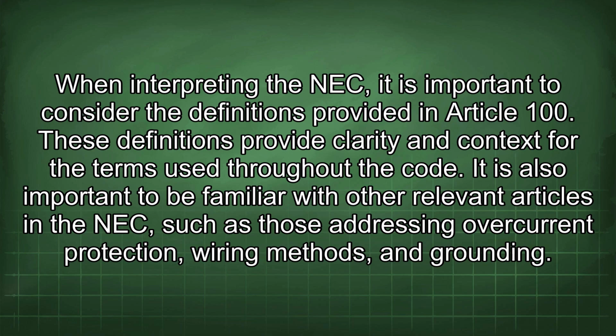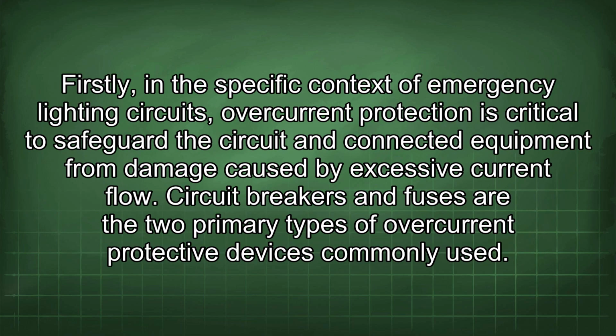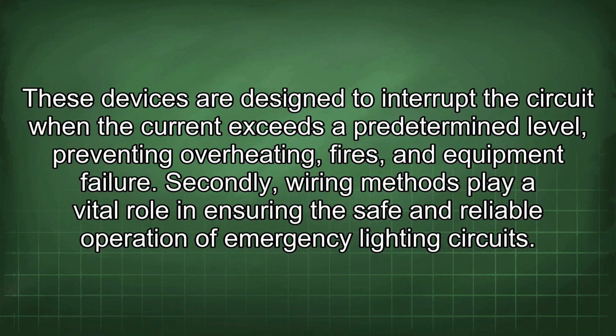It is also important to be familiar with other relevant articles in the NEC, such as those addressing overcurrent protection, wiring methods, and grounding. Firstly, in the specific context of emergency lighting circuits, overcurrent protection is critical to safeguard the circuit and connected equipment from damage caused by excessive current flow. Circuit breakers and fuses are the two primary types of overcurrent protective devices commonly used.